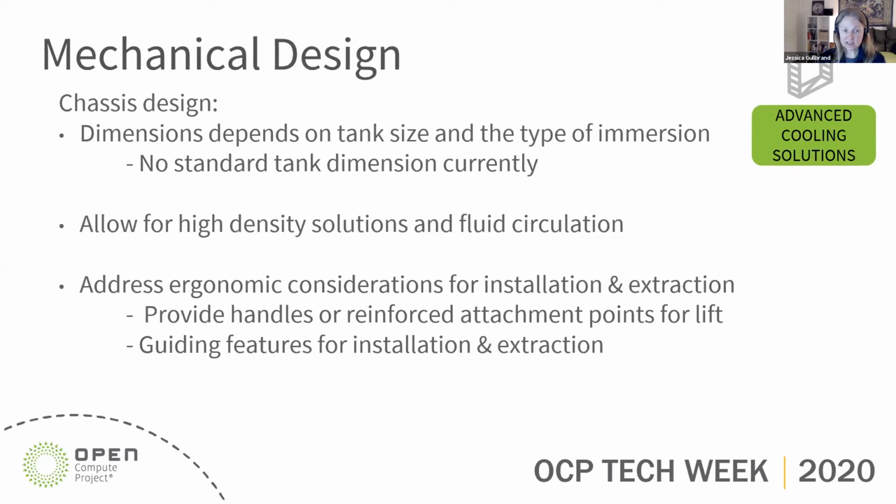There are no standard tank dimensions currently. You can get tanks that are more of the standard 19-inch or 21-inch server size. However, there's not a standard depth of those tanks, which is good to be aware of, and it can be customized to what the customer wants.